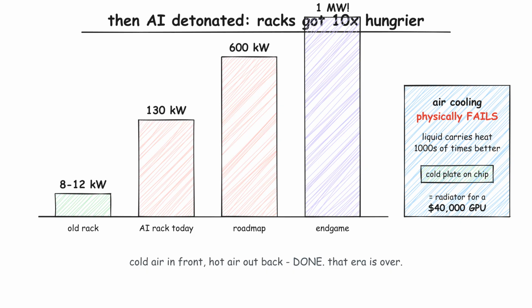At those densities, air simply stops being a usable tool. Air is a lousy carrier of heat. At 130 kilowatts, you cannot physically push enough of it through a cabinet, and the fans trying would devour a fortune in electricity themselves. Liquid is thousands of times better at carrying heat away, so the industry is switching to liquid cooling. A metal plate laced with tiny channels sits directly on the chip, coolant runs through it, and the heat leaves through pipes, a radiator system, except the engine it protects is a $40,000 GPU.